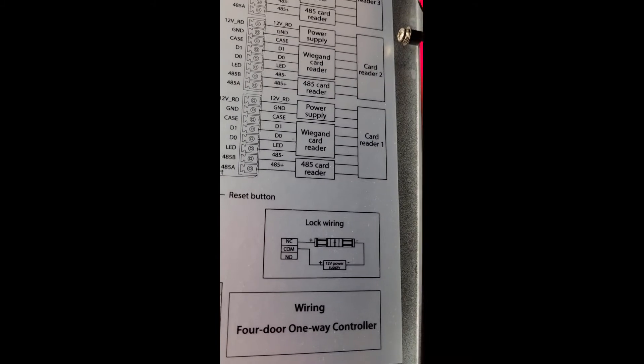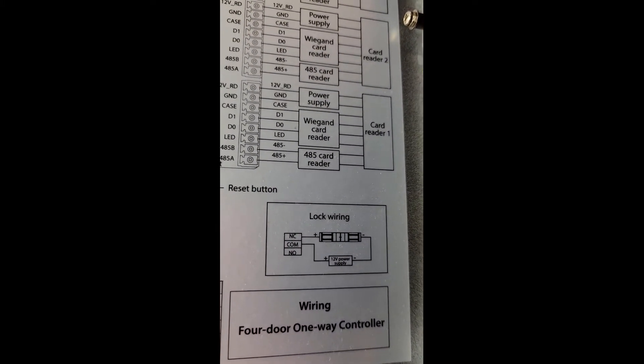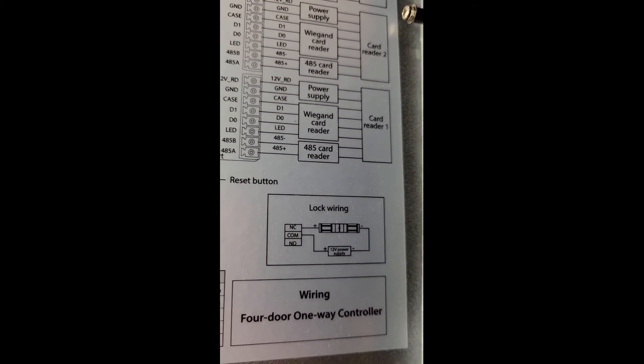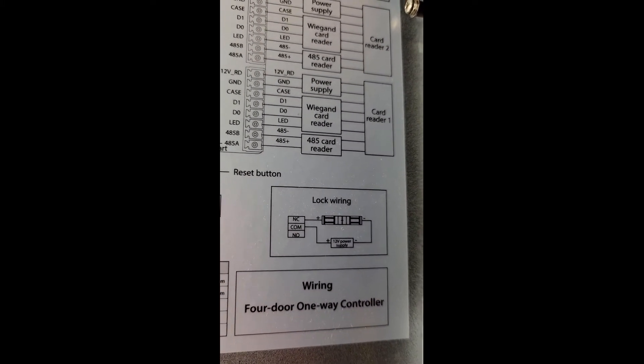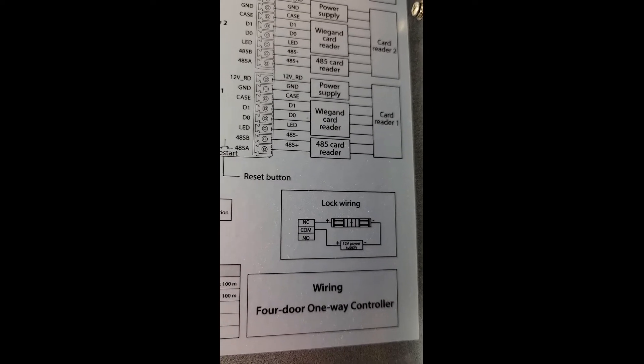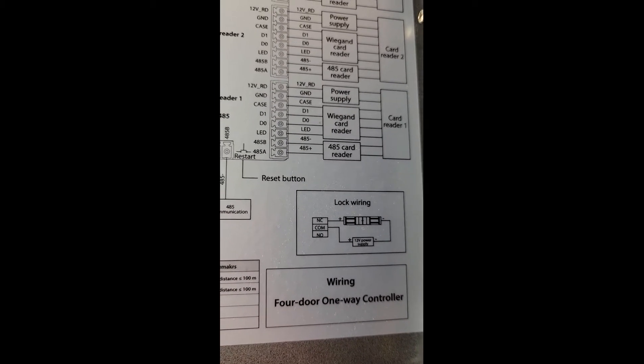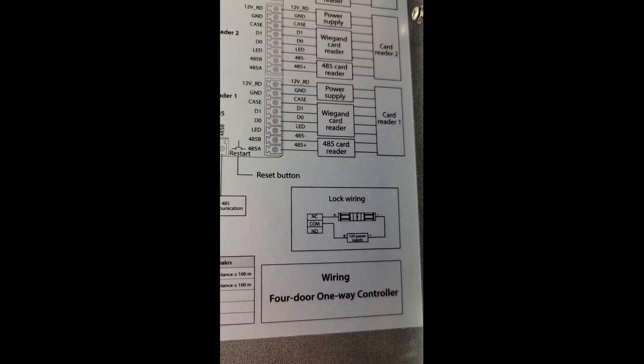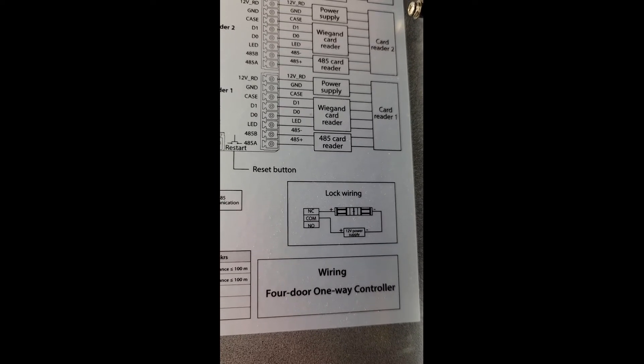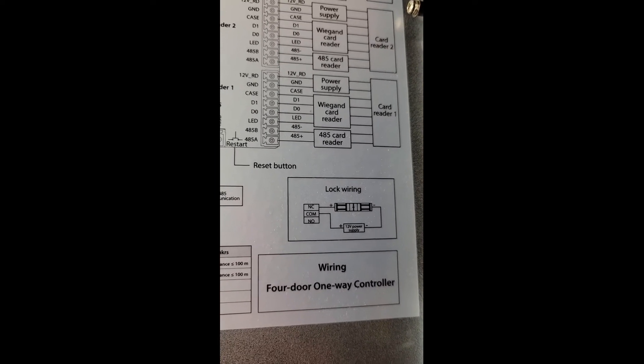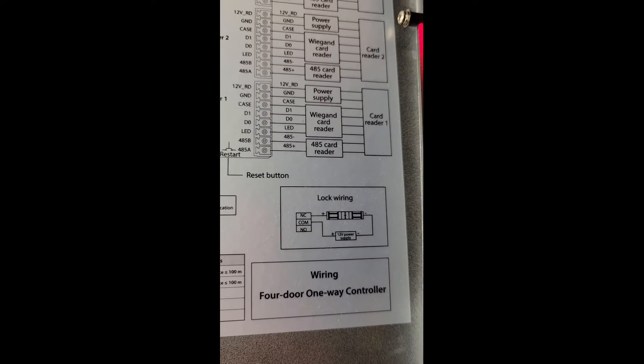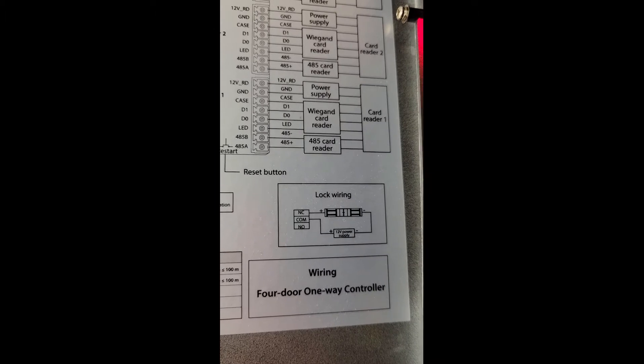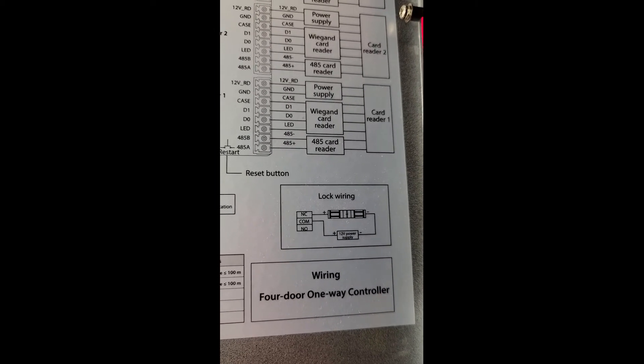And then we're going to be doing the card reader one terminal. So for card reader one, we're going to do an RS-485 connection. We will utilize four wires from the reader. The red and black from the reader will go to the power supply portion, and then the yellow and purple from the reader goes to the RS-485.